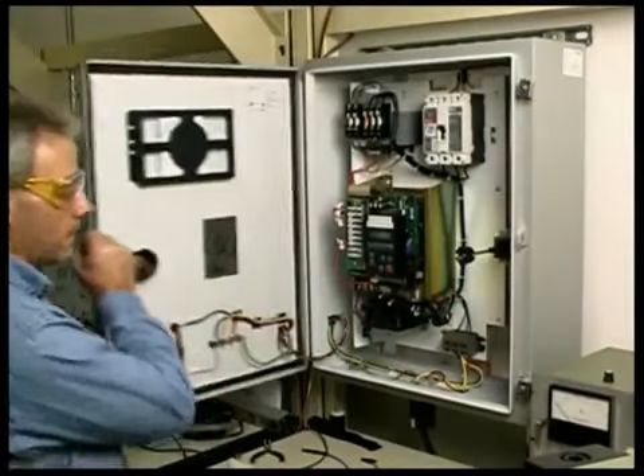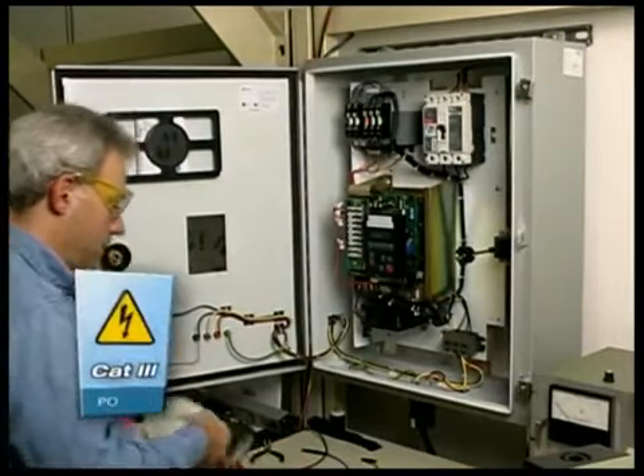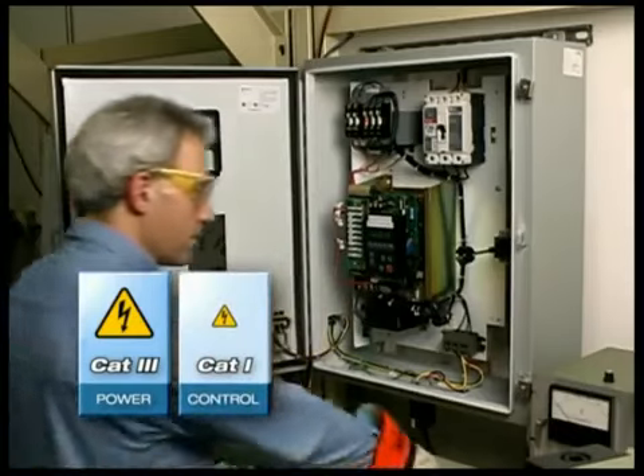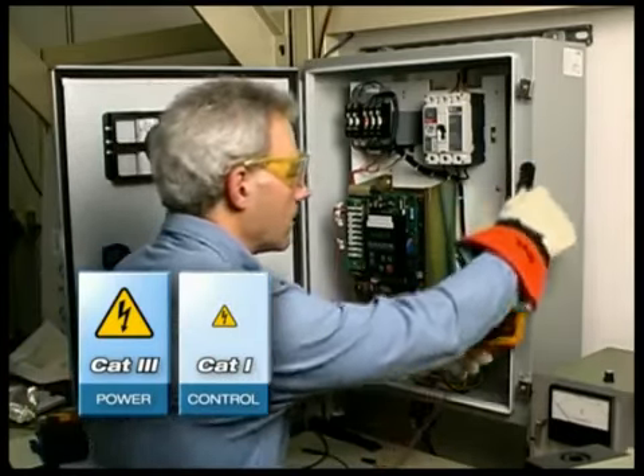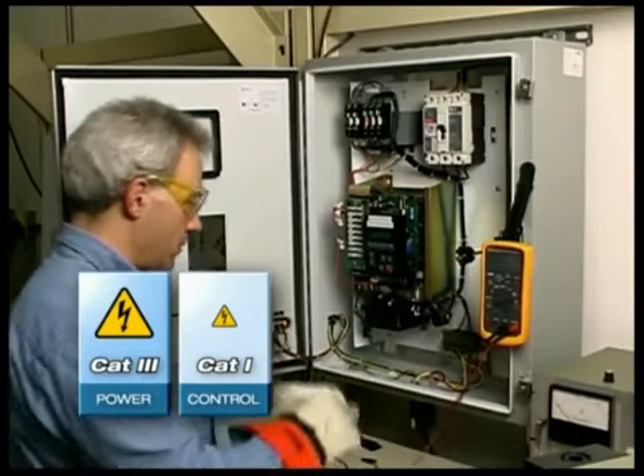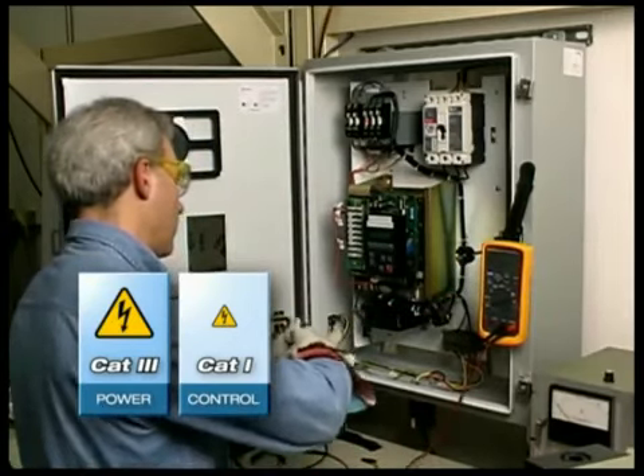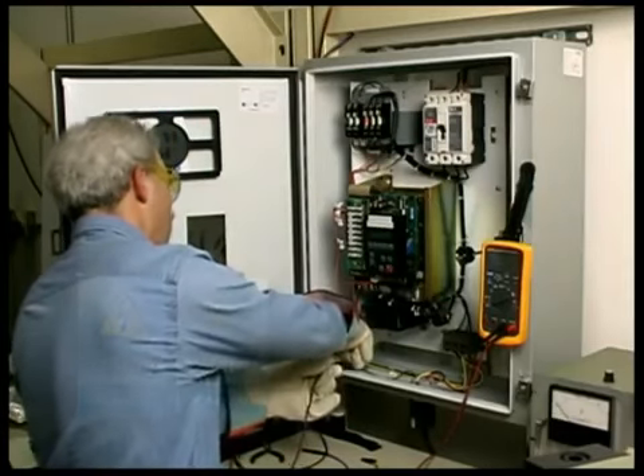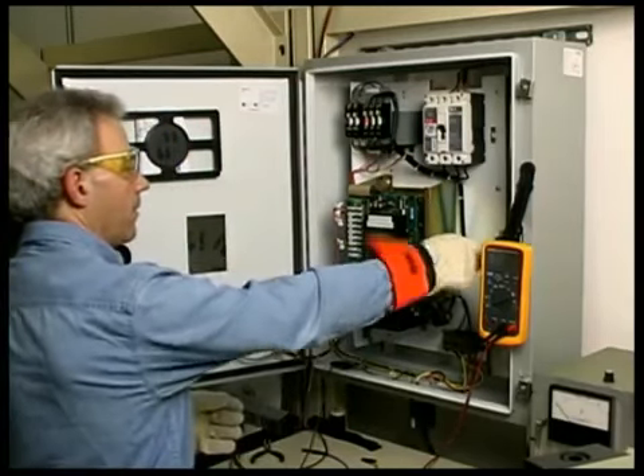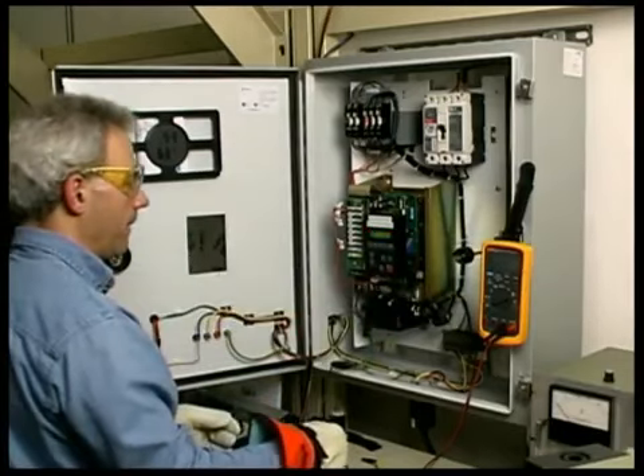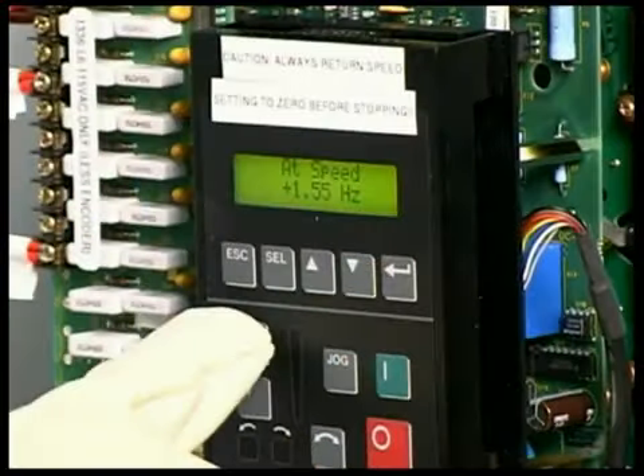Some installations include multiple categories. This motor drive panel is Cat 3 on the 400-volt power side, and Cat 1 on the control side. Here, you should use the higher-rated Cat 3 meter. In general, where greater fault currents are available and voltage transients increase, measurement becomes more hazardous. This means a higher Cat rating. If you're working in a Cat 3 or Cat 4 environment, you should be using test equipment rated 600 or 1000-volt Cat 3 or 600-volt Cat 4.